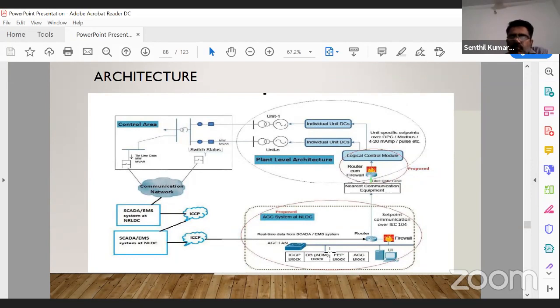We are not going to pick up the generator's full generation; we have to pick up the generation partially only, up to 10%. Suppose one generator is 210 megawatts - then 10%, or 21 megawatts, is the only allowable amount to pick up for AGC, automatic generation control.